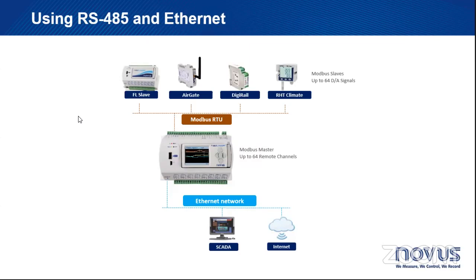Also, this is a very common case that I'm sharing with you. Besides being a Modbus RTU master, the field logger can also be an interface between what you have on the higher level on the Ethernet network and what you have on the floor, on the factory floor. So in this case, I have a SCADA system, okay, that is inquiring directly from those devices, for example DigiRail or RHT Climate, through the field logger. The field logger, at the same time it is a Modbus RTU master, could be as well a Modbus gateway, Modbus TCP to Modbus RTU. So the SCADA sends the command, the field logger translates it into RTU, sends it to the device, the device answers, the field logger retranslates it and sends it to the SCADA system.